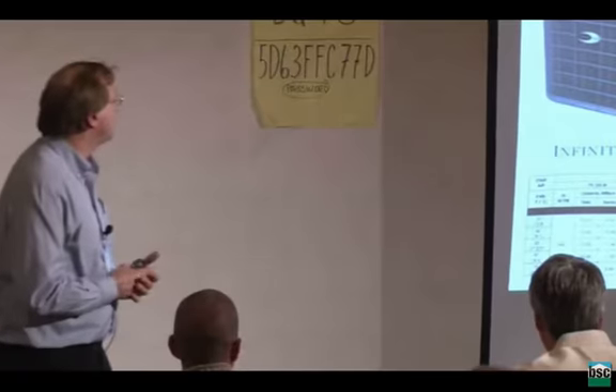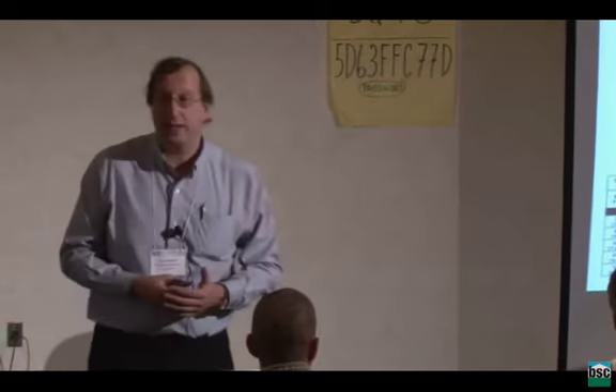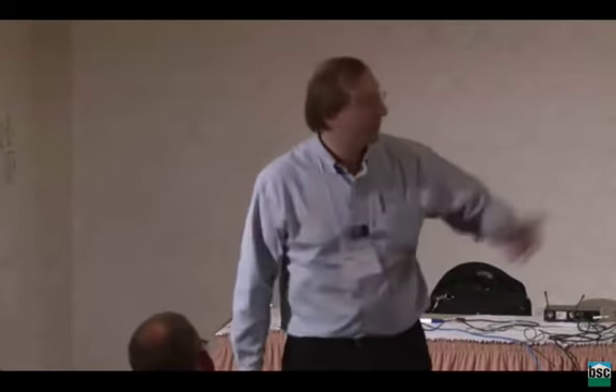The COP is still somewhat limited, but if I were to look at, say, the Waterloo, Ontario climate, let's pretend I have, on an hour-by-hour basis, a low-load house that this heat pump could heat, over the whole winter heating season, I get a seasonal COP of 2.9, something like that. But this unit doesn't cost me $3,000, it costs me $6,000, plus install, right? These are material plus install. So, yeah, it works, but it's more expensive. But it's an all-electric solution. So if you're on a net zero energy house, or you don't want to do conversions from gas to electrical energy, you can buy one of these. Okay. Any questions about those basic systems?